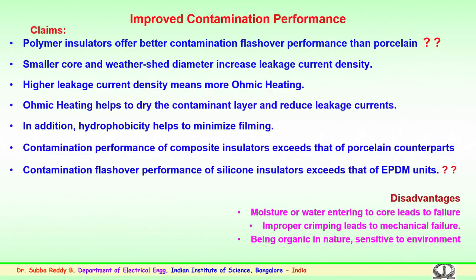And the third limitation is, as mentioned, that polymer insulators, being organic in nature, are sensitive to the environment. So, the environment plays a very important role for the overhead transmission system. The line where it is passing and the climatic conditions of the area where the tower is situated, where the insulators are placed, all play a role. We will further look into the various environmental parameters which could cause serious issues to insulators in service.